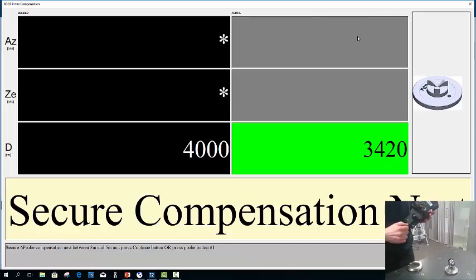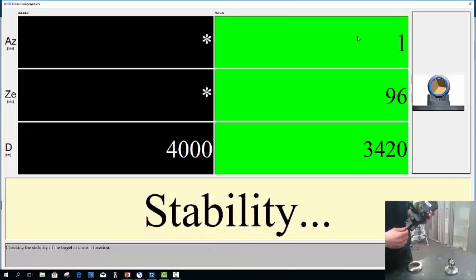In this case, secure the compensation nest. It's important to make sure the compensation nest is on a secure, stable table, ensuring that there's no chance of it moving during the procedure. If movement takes place, the chances are that the 6Probe compensation will fail. When you've got the nest secured, you can click number 1 on the side of the device, and that will move on to the next command, which is to switch to the 1.5" SMR.